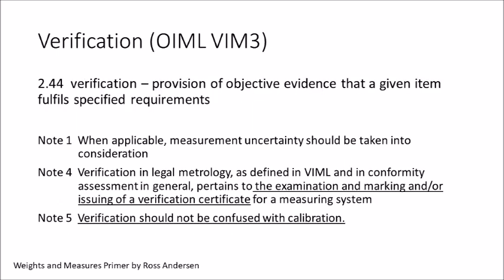This is a definition of verification taken from the VIM, the International Vocabulary of Measurement, 3rd edition. And you see this is very similar, but it doesn't split the specified requirements into two pieces. But what's interesting about this definition is note 5, where it says verification should not be confused with calibration. And I think that's what we explained earlier.